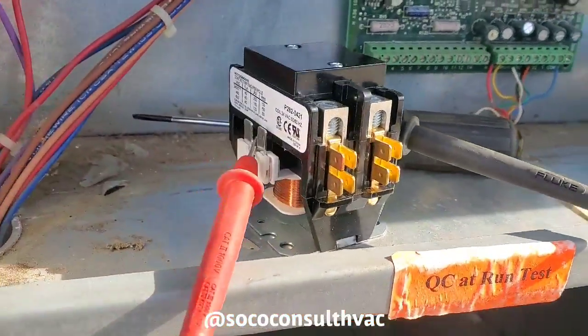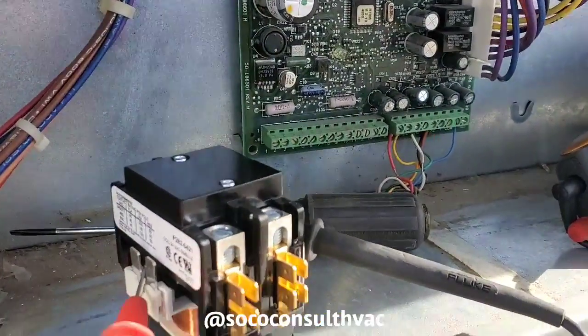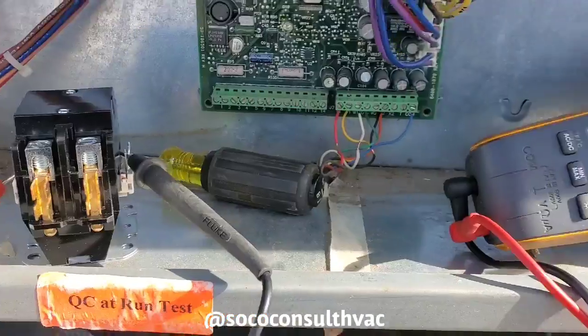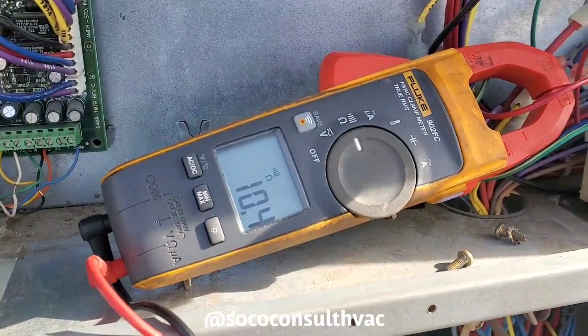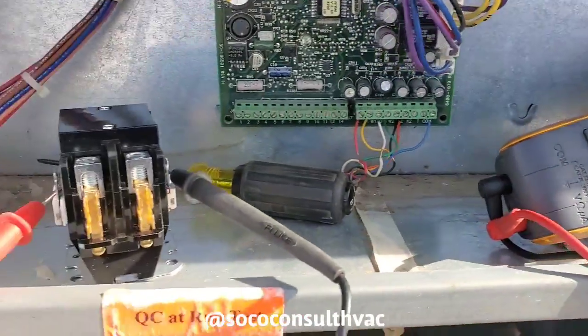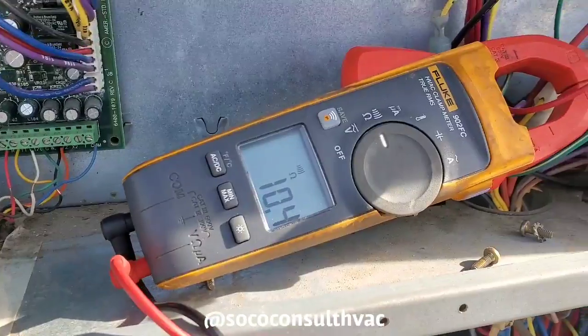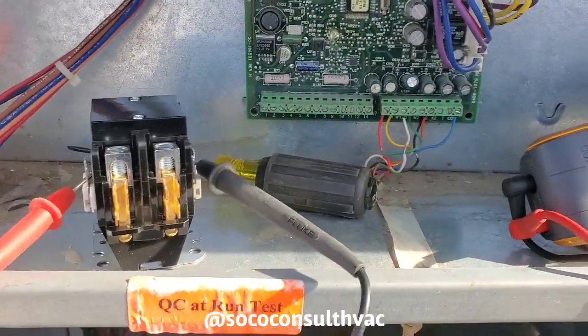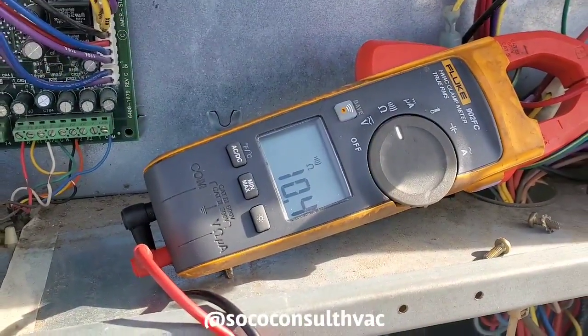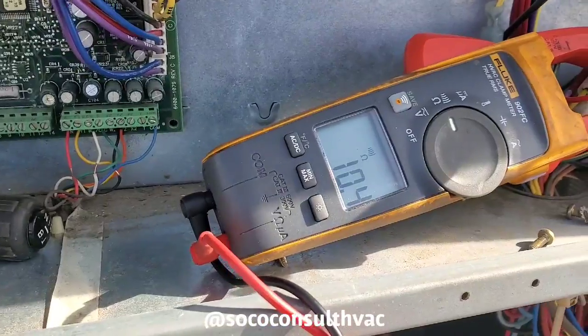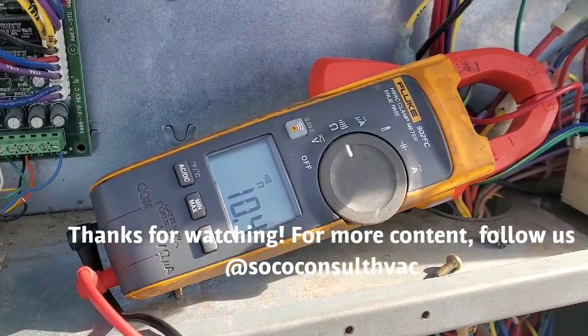But this is your typical 40 full load amp contactor that you would see in light commercial, residential. That's pretty standard. I mean, if you're ohming out a contactor and it's ohming out at 100 ohms, or it's ohming out at 0.2 ohms, then you know that's probably way off. But somewhere around 10 ohms seems to be the normal thing that you would read.